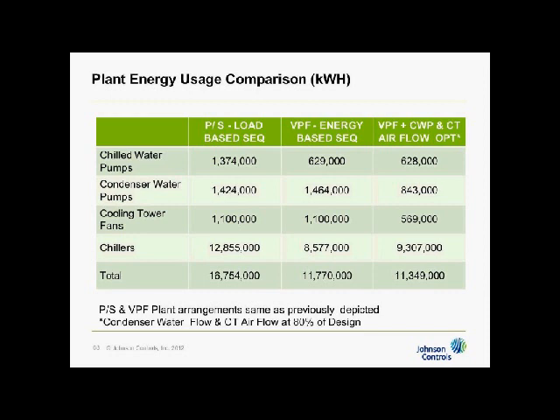As expected, the reduced condenser water flow, the reduced cooling tower fan flow, and the increased fouling from reduced cooling tower water flow caused an increase in chiller energy. We went from 8.6 million up to 9.3 million. However, as we were interested to find, the total net energy for that plant went from 11.8 million kilowatt hours down to 11,349,000 kilowatt hours in that year.